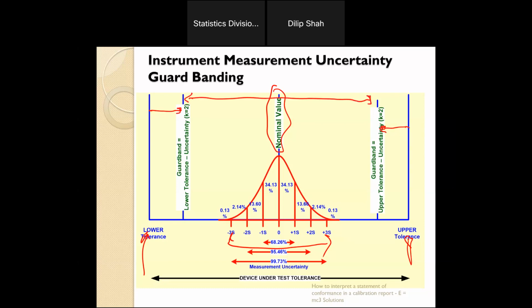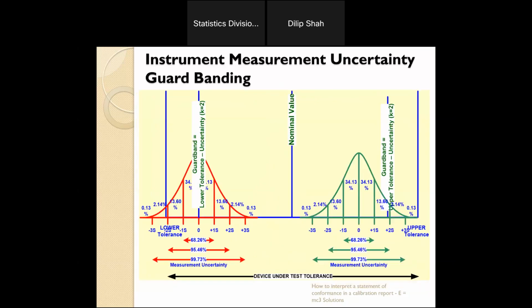So if my measurement falls within the acceptance limit, then I can live with that measurement with the risk associated with it. And this region is called the guard band region. I've shown you the example. Obviously the green measurement here is within my acceptance limit, which is fine. This second one here is right at the acceptance limit.